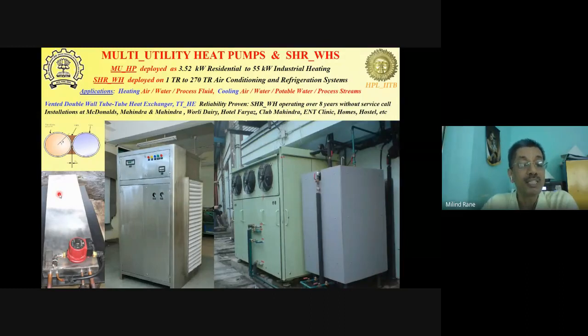Now, this superheat recovery technology is not new. Even in the 1970s, when the first oil crisis hit the world, these types of heat exchangers were being imported by some of our top refrigeration and air conditioning industries in the country. But these systems were based on shell and tube heat exchangers, and they led to leakages and mixing of the refrigerant and the water being heated, potable water being heated. And if the water leaked into the refrigeration circuit, the entire refrigeration system had to be shut down. It had to be cleaned up thoroughly and then restarted, which was a major catastrophe as far as the hotels or industrial plants were concerned, and no chief engineer or plant operator would be happy to get into that kind of situation. So although the potential for energy saving was phenomenal, and the monetary saving was very good, because of reliability issues these systems were not being used extensively.